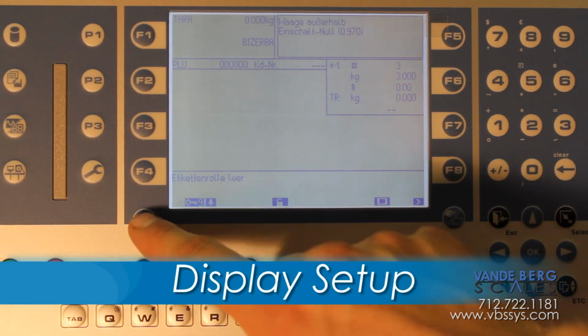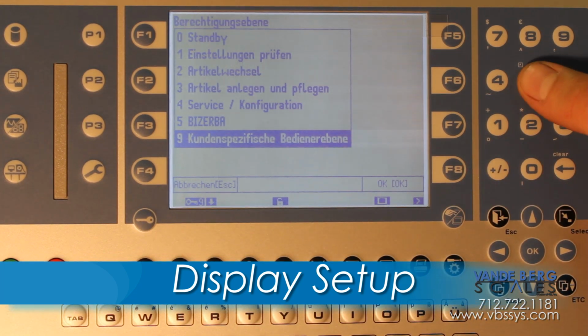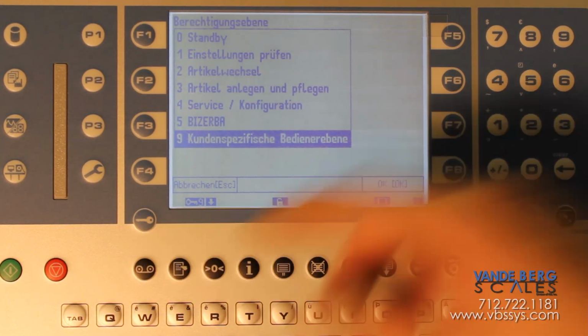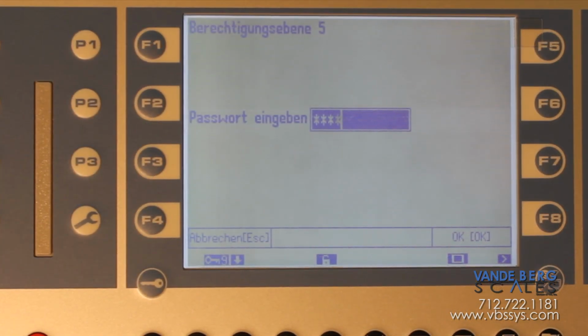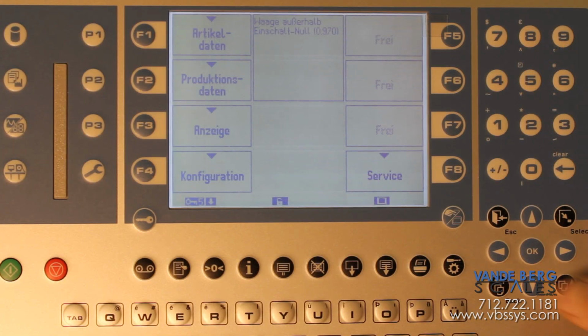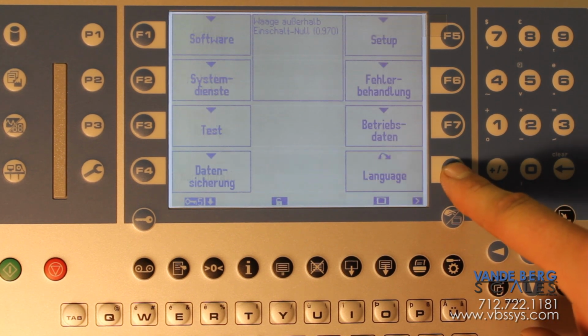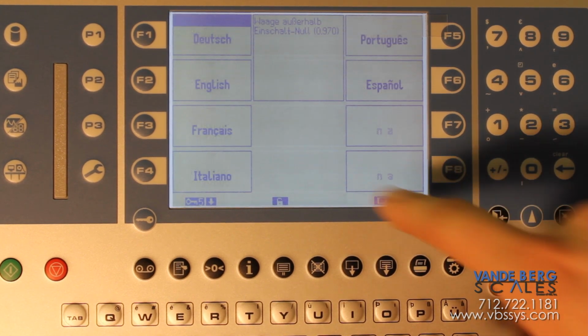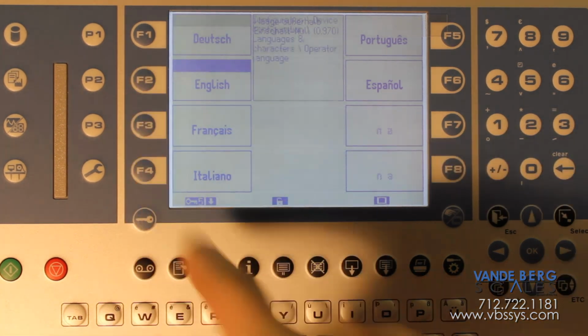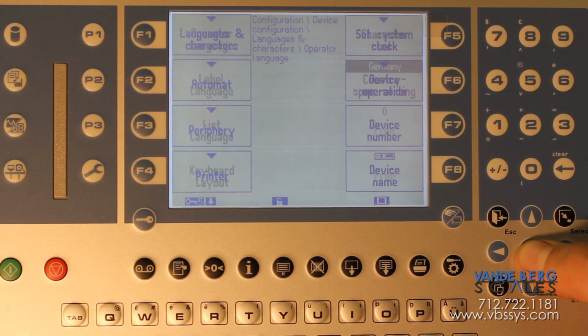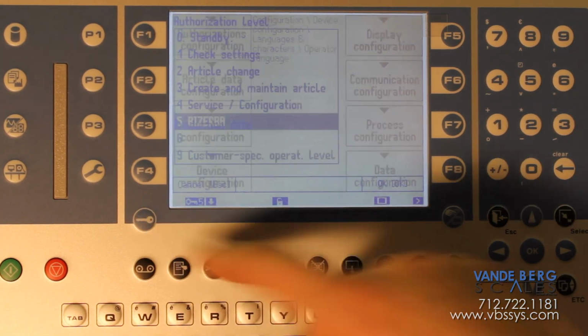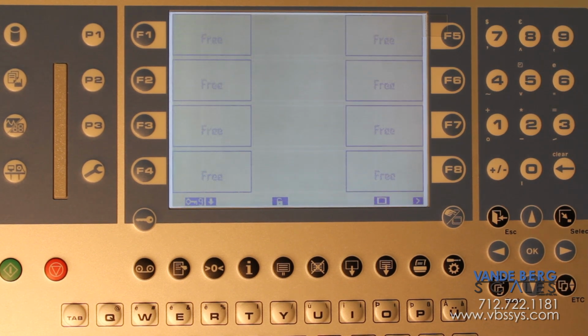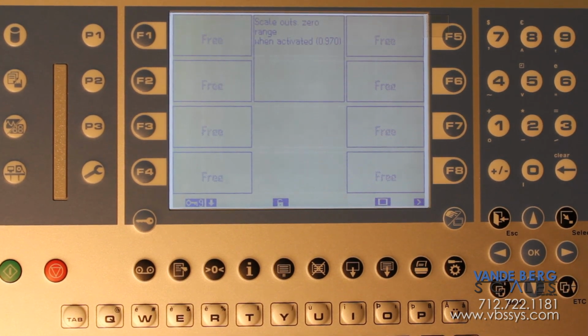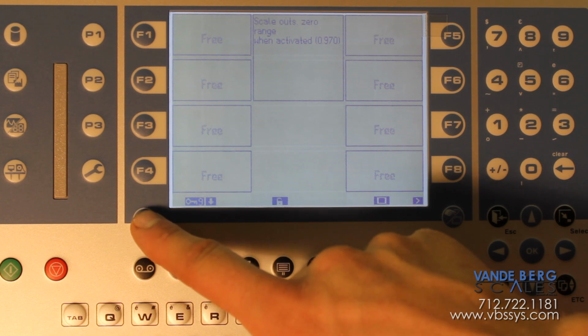The machine is default in German, so we'll go to mode 5 by pressing the key button and then pushing 5 and entering the password. We'll then go to service, language, and then change it to English. And then press OK till you get back. Now that we changed the language, we're ready to start setting up the scale and doing the scale configuration.